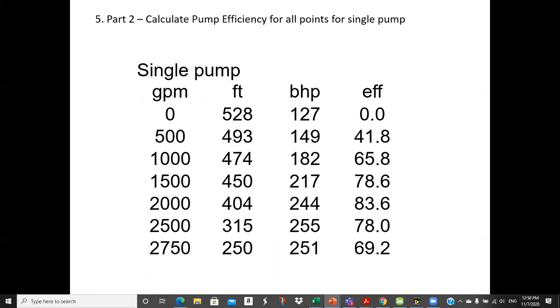You're given the first 3 columns, and so the efficiency is the water horsepower divided by the brake horsepower, and the water horsepower is GPM times feet of head, divided by 3960. Okay, and so it's pretty simple. For example, on the 500 GPM point, if I take 500 times the feet of head, 493, divided by 3960, that's 62.25. And if I divide that by the brake horsepower, 149, I get the efficiency.